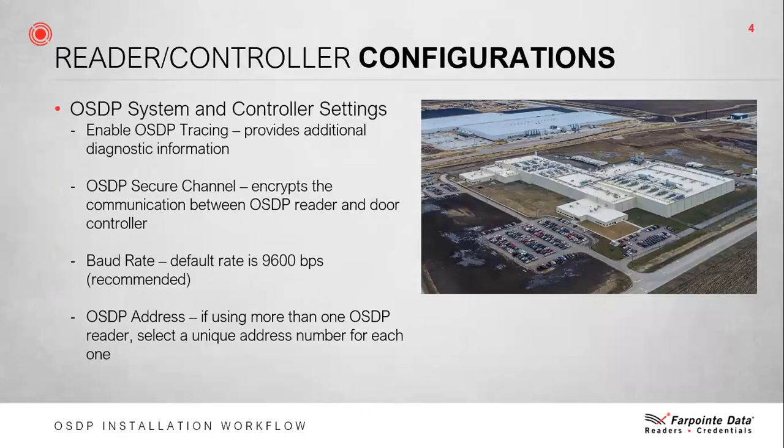Reader and Controller Configurations. Once you've agreed on the overall system details with your end users and are ready to move forward, you need to determine the OSDP capabilities of the system you're installing and how you plan to configure the communication between the controller and the readers. Configuration starts at the system software. Some of the more common OSDP settings include: enable OSDP tracing, which provides additional diagnostic information from the device wired to the controller if the software supports it; and OSDP secure channel, which encrypts the communication channel between the OSDP reader and the door controller.